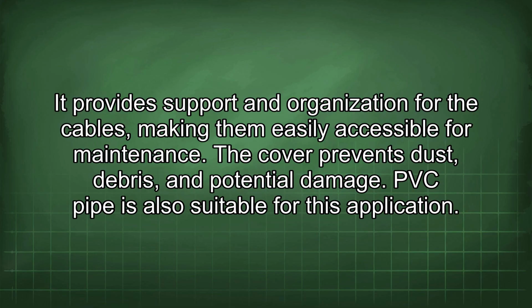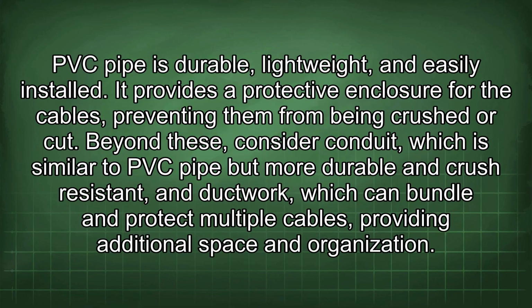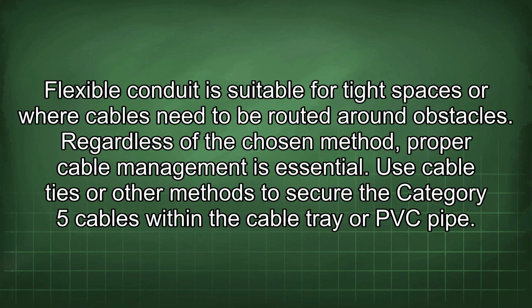PVC pipe is also suitable for this application. PVC pipe is durable, lightweight, and easily installed. It provides a protective enclosure for the cables, preventing them from being crushed or cut. Beyond these, consider conduit, which is similar to PVC pipe but more durable and crush-resistant, and ductwork, which can bundle and protect multiple cables, providing additional space and organization. Flexible conduit is suitable for tight spaces or where cables need to be routed around obstacles.